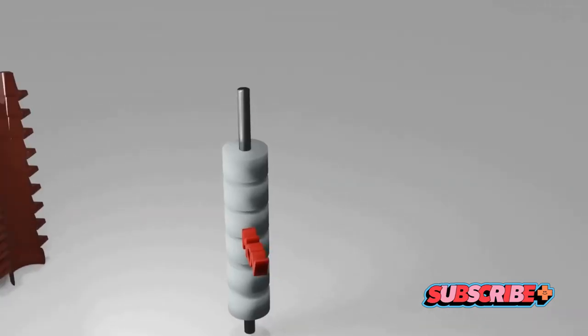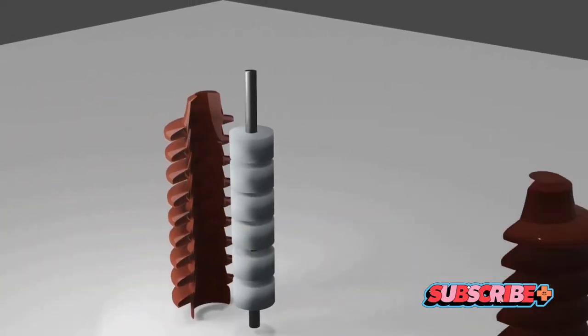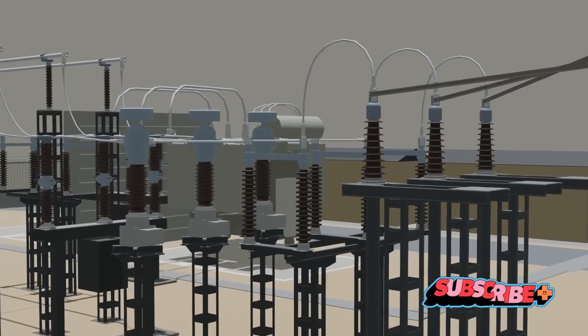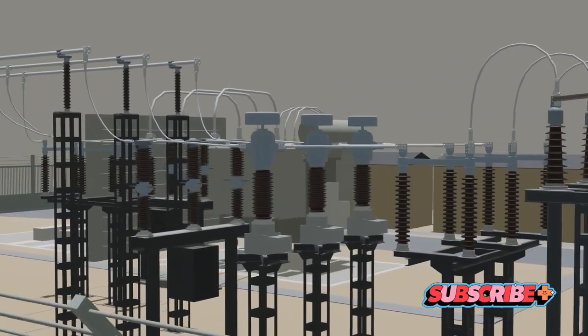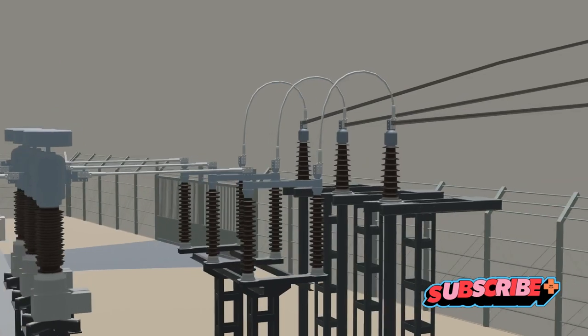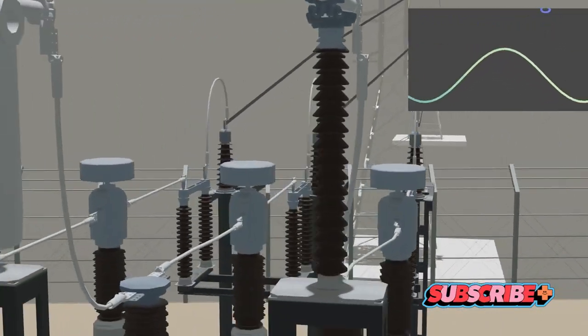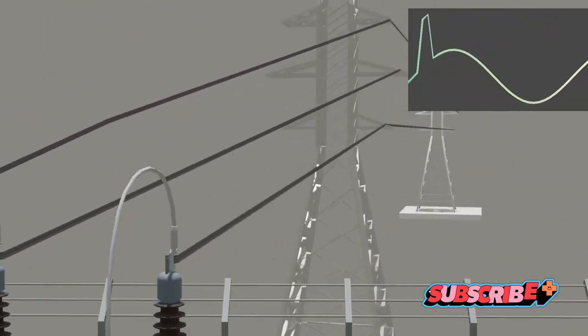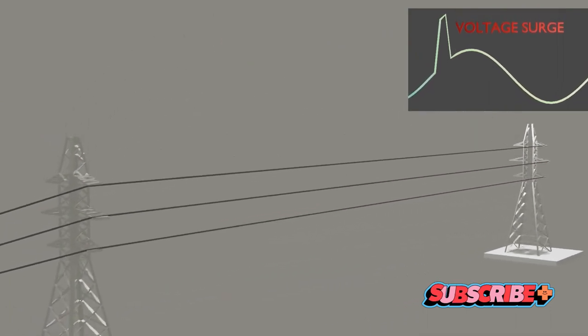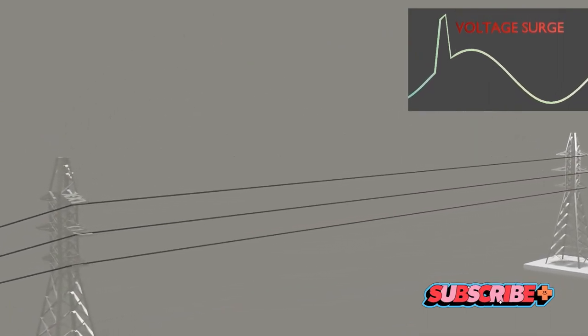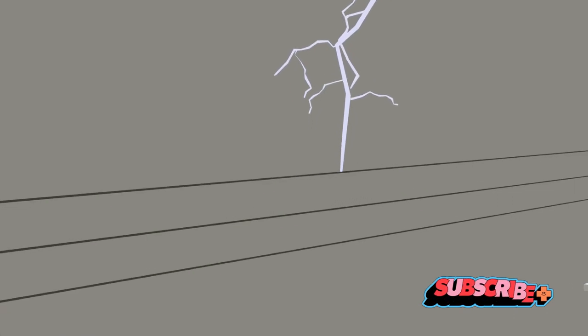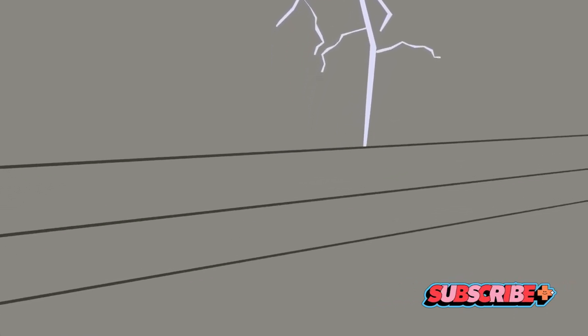The heart of a surge arrestor is a component called the metal oxide varistor, or MOV for short. This is the hero of our story, the part that does the heavy lifting. The MOV is a semiconductor, a material that can conduct electricity under certain conditions but not others. Under normal circumstances, the MOV is a poor conductor, allowing only a tiny trickle of electricity through. But when a voltage surge hits, the MOV springs into action. It suddenly becomes a good conductor, allowing the excess voltage to pass through. It's like a switch that flips on when the voltage gets too high.